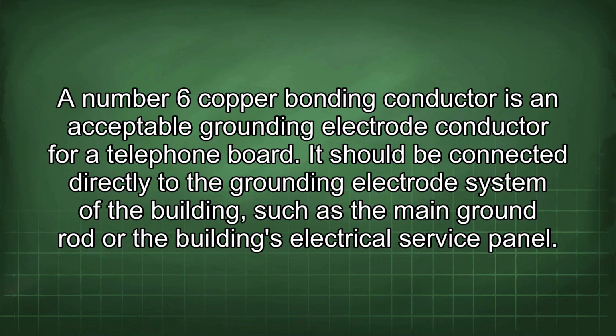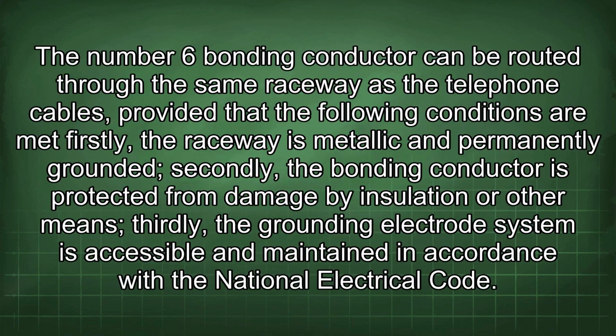A number 6 copper bonding conductor is an acceptable grounding electrode conductor for a telephone board. It should be connected directly to the grounding electrode system of the building, such as the main ground rod or the building's electrical service panel.